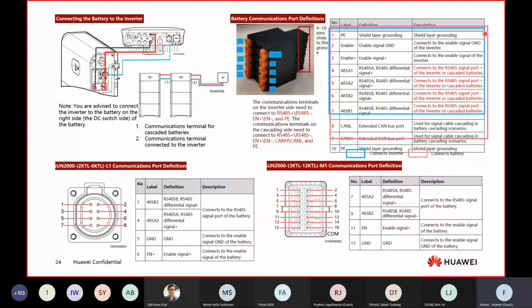You can see the blue color marking here connects to the inverter, and the red color marking connects to the battery. This is the pin layout for the COM port for L1, with 8 pins total. For communication to the battery, we use pin number 3 and number 4, and this one is for the enable signal. If you forget to install this, normally the inverter won't send the signal to the Luna 2000 to operate, since the Luna receives commands from the inverter through this signal cable.